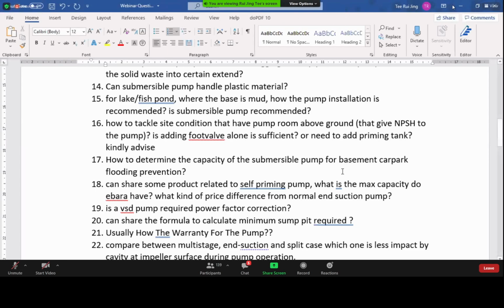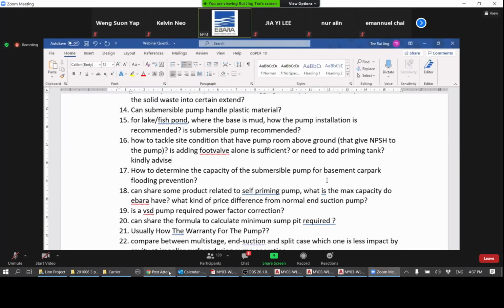Do we need to add a priming tank? It depends again on your application. For fire systems, a priming tank is a must because it is in the regulation, and you want to ensure that when the pump starts, no matter how you have water, a priming tank is needed. In some cases, I've seen that people do not put a priming tank, but if you want a straightforward answer, yes, a priming tank is always better because that ensures that the pump is always primed before you start.